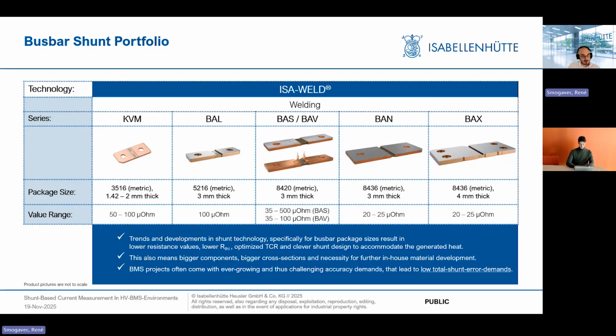Obviously, depending also on the terminal temperature, because with the headroom between the max terminal temperature and the 170 degrees max temperature limit specified, you know how much the shunt can heat up itself, to know how much current is allowed to go through to not exceed 170 degrees.